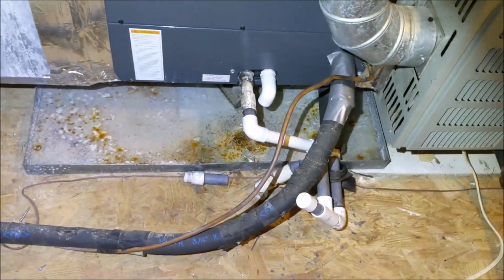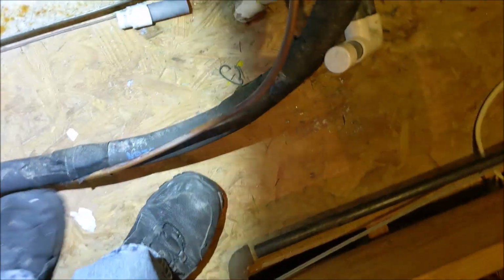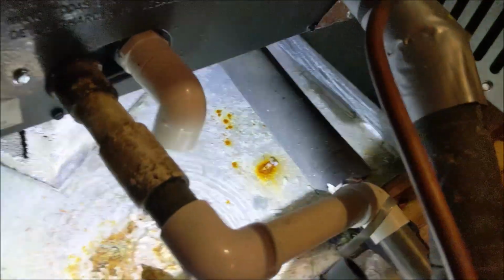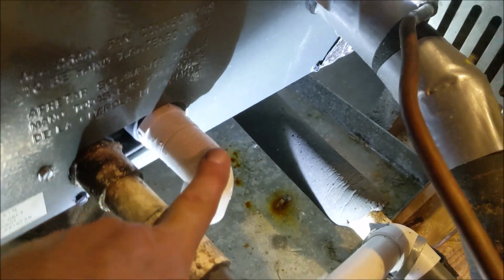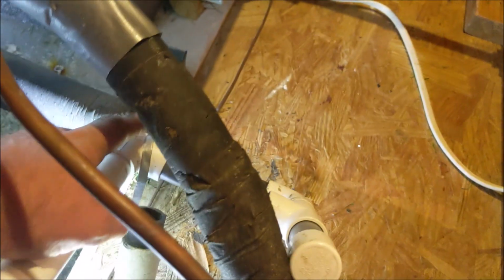All right, we're still in the attic, right off the stairs, come up to the room, and we have a gas furnace and evaporator coil, and inside that pan you can see that the pan is filled with water. And this is what I've seen outside. So let's take a look here. This is the primary, this is the secondary. We'll take a look at the primary line.